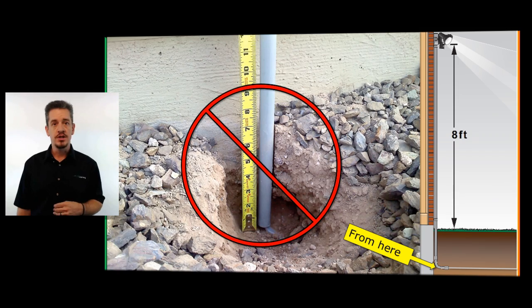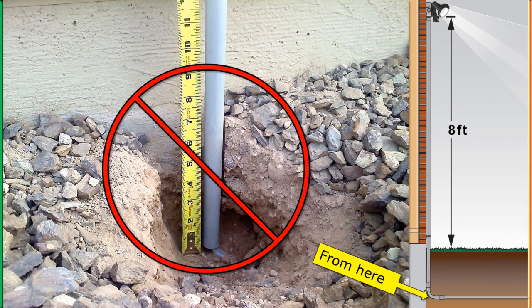Now unfortunately, this is what we see a great majority of the time. There's a couple different problems here. Number one, look at that cable, that UF cable coming up into the bottom of that raceway.